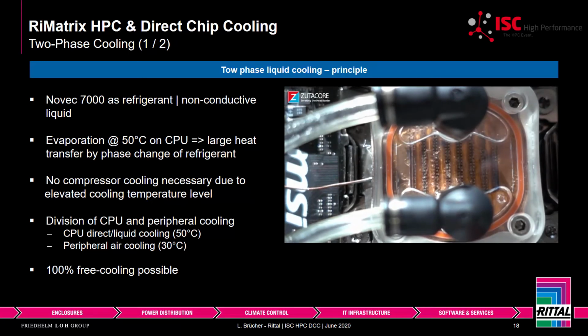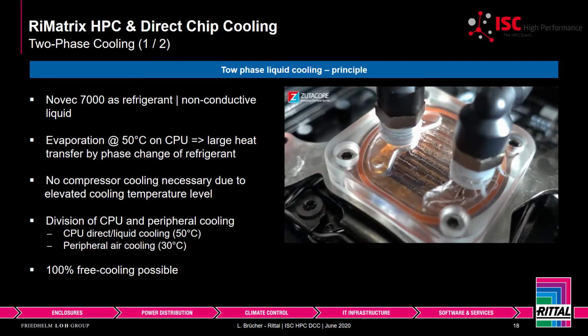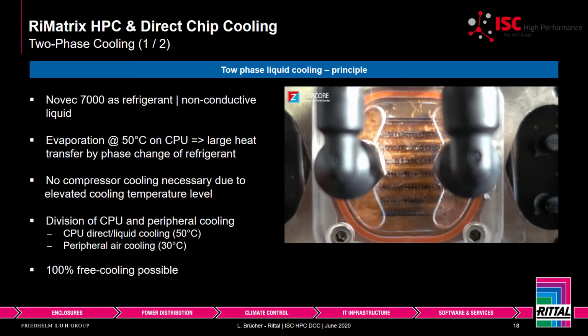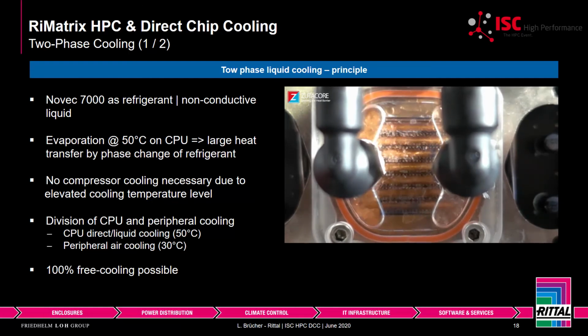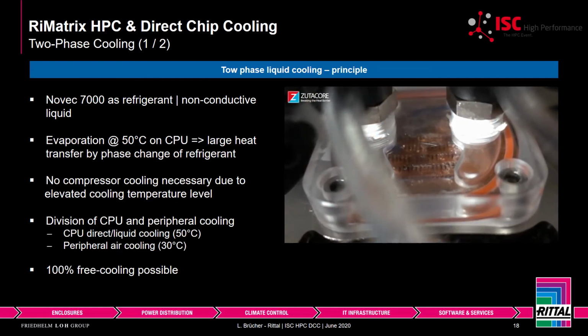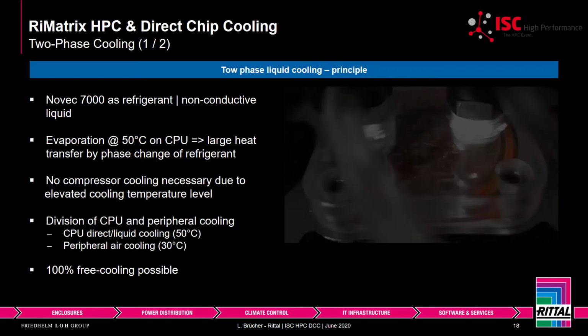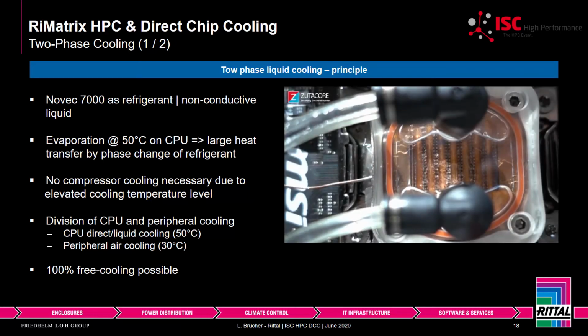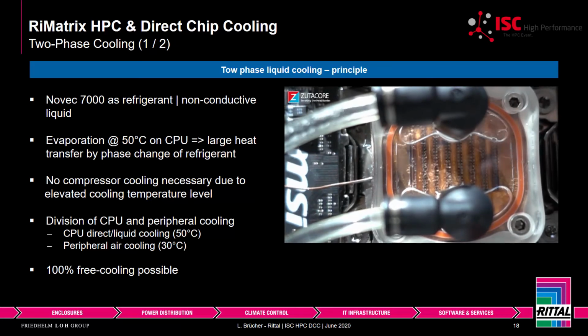The solution uses Novec 7000 as a refrigerant. This is the first exciting news because you have no water in the server, just a non-conductive liquid. There is no risk of water spillage possibly damaging servers. Also, the evaporation occurs at 50 degrees Celsius, which has the benefit first that you have a high temperature. So it means you could really work 100% of the year with free cooling.